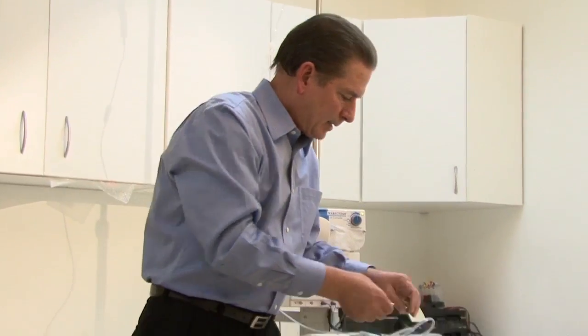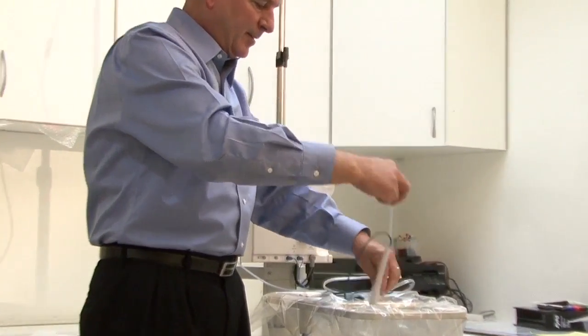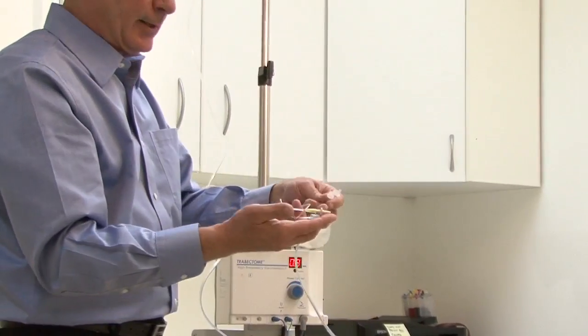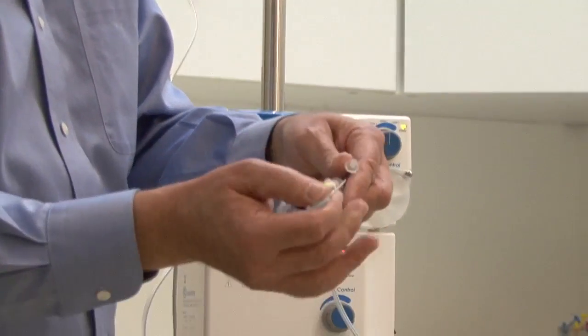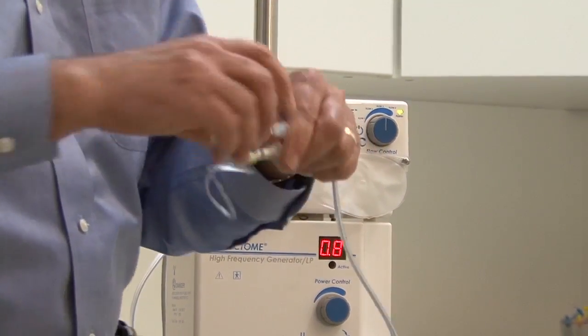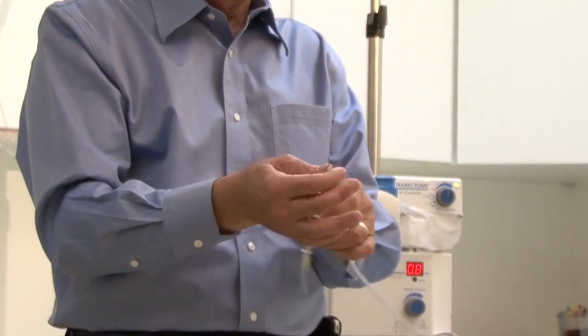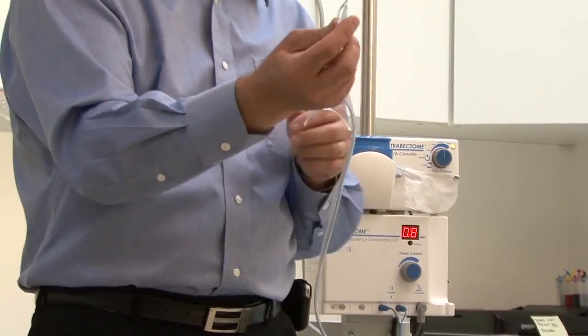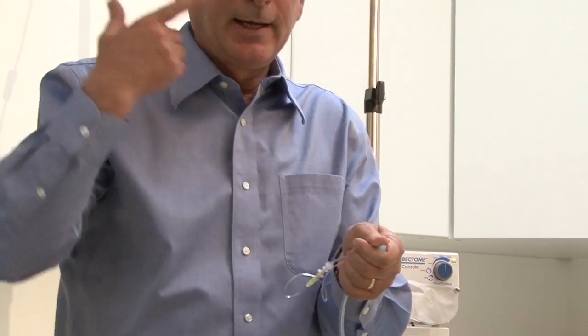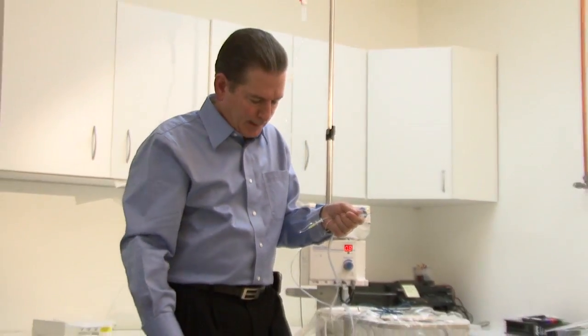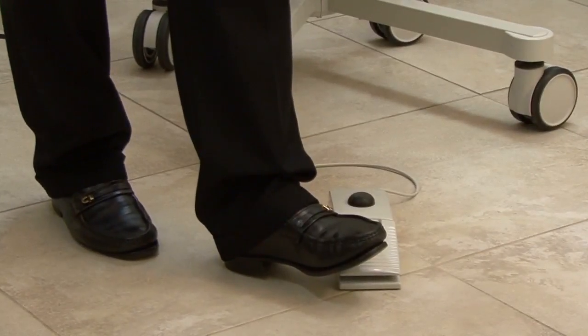And again, what we do is we just disconnect the handpiece and set it aside so that we can connect the little IA cannula to the fluidic set. Again, it only connects one way, and there's no priming or anything that needs to be done.